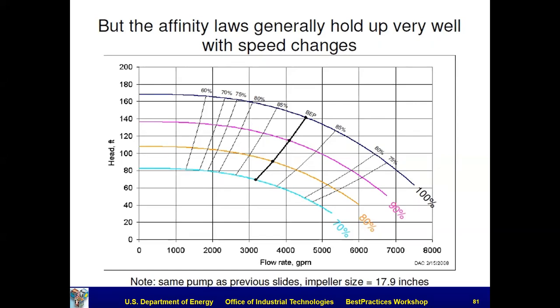The head goes with that ratio squared. So then I would take 0.9 squared, which would be 0.81. 0.81 times this 80 feet of head gives me the head at this point. And so then this point will shrink down to this point. So you take all of your points and you shrink them down, and then you redraw the curve. And so you can plot a pump curve at any speed you want using the affinity laws, and that's appropriate.